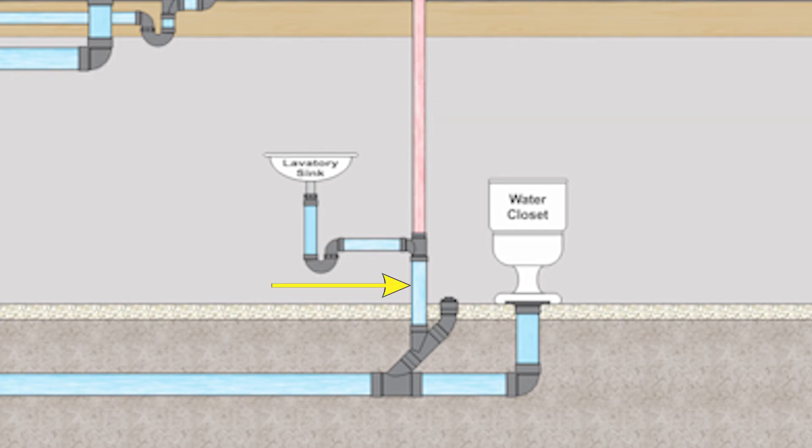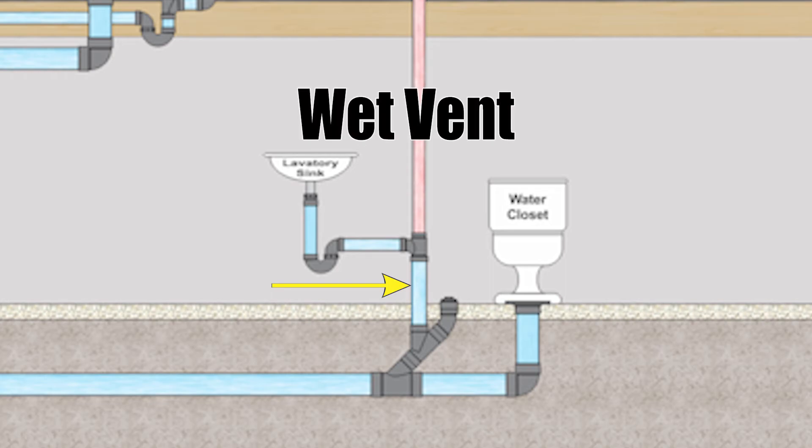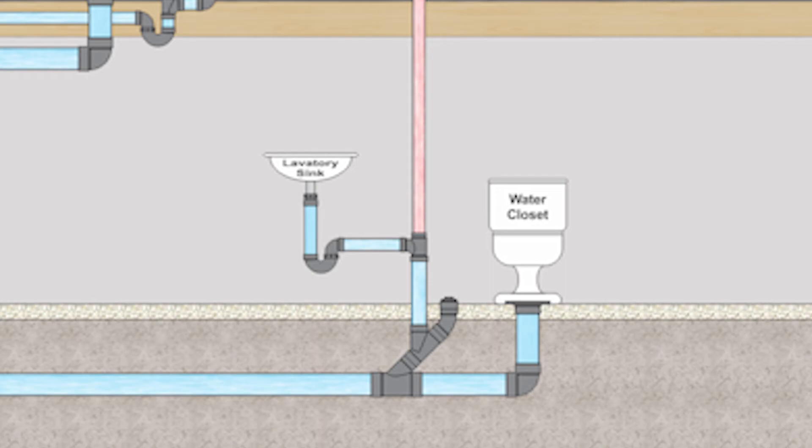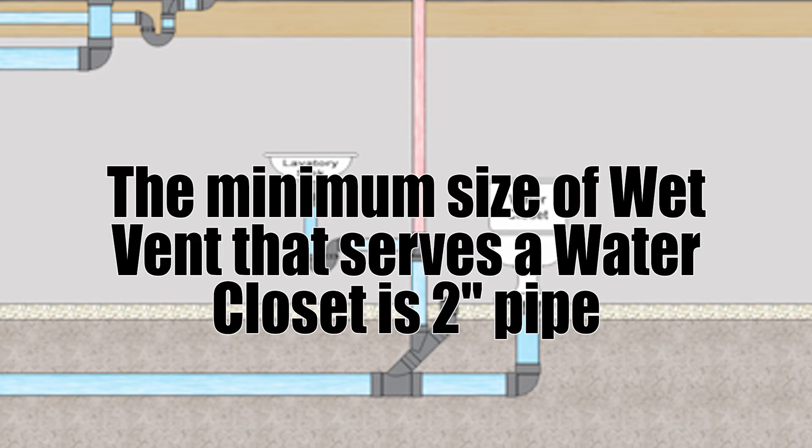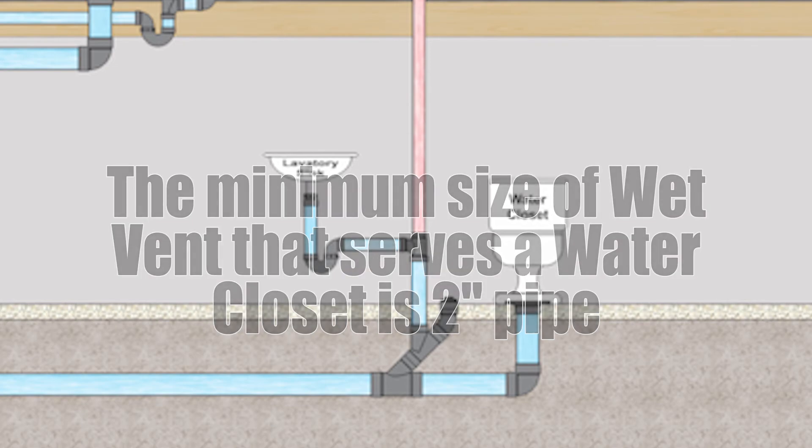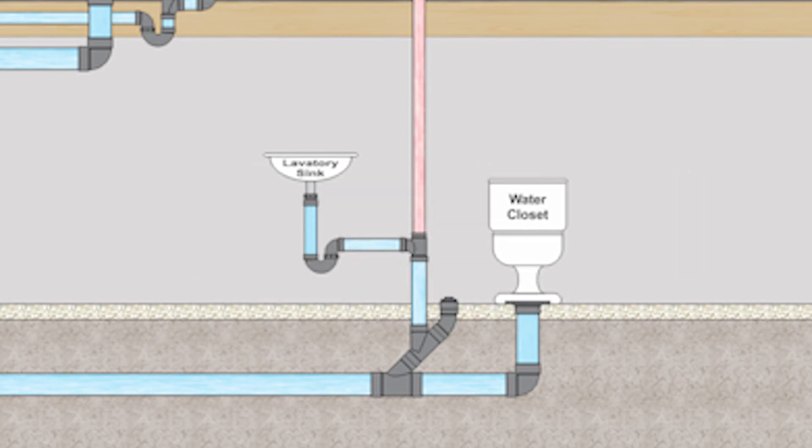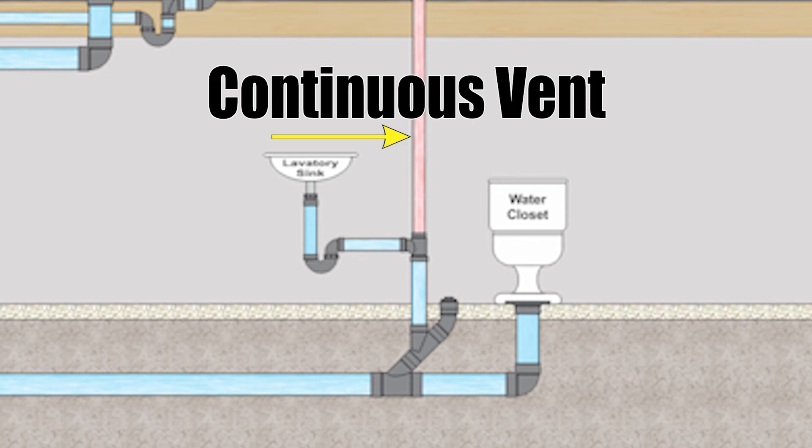If you'll look the water closet has no vent or better yet it does but it goes through a drain that comes down from that lavatory sink. We call that a wet vent meaning it's a pipe big enough to act as a drain and a vent at the same time. The minimum size of a wet vent serving a water closet is two inch. Now wet venting is rather involved and has many codes around it so what we're going to do is take care of that in its own video series.